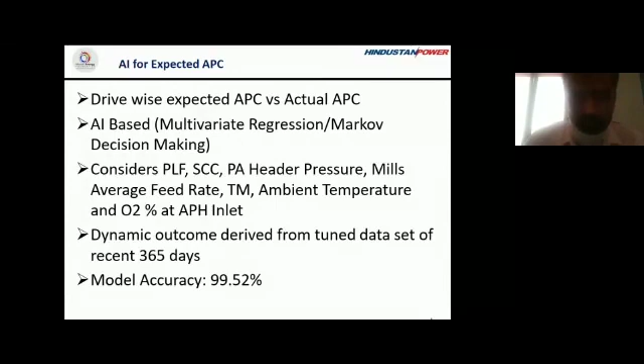The first among the measures is measuring the aux power consumption on a station basis. We have used our in-house developed Markov decision making based and multivariate regression analysis based model, which considers the plant load factor, specific coal consumption, PA header pressure, mill's average feed rate, total moisture, ambient temperature, and O2 at APH inlet as dependent variables to forecast the expected APC on a drive basis, considering the last historical 365 days of data. We found that the sum of squares of errors, which is broadly the accuracy of the model, that we have achieved is 99.52%.